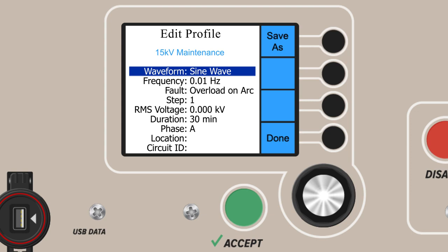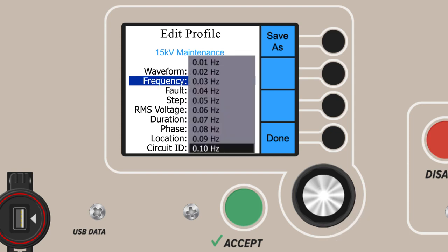Now it's time to choose the parameters of the test. First, choose your waveform type from sine, square, or DC positive or negative. We'll choose sine wave. Now, set your frequency in Hertz. Conventionally, we'd test at the highest possible frequency, at 0.1 Hertz. However, slower frequencies down to 0.01 Hertz are included for the testing of higher capacitance loads, such as longer cable lengths. We'll set ours at 0.1 Hertz for now.